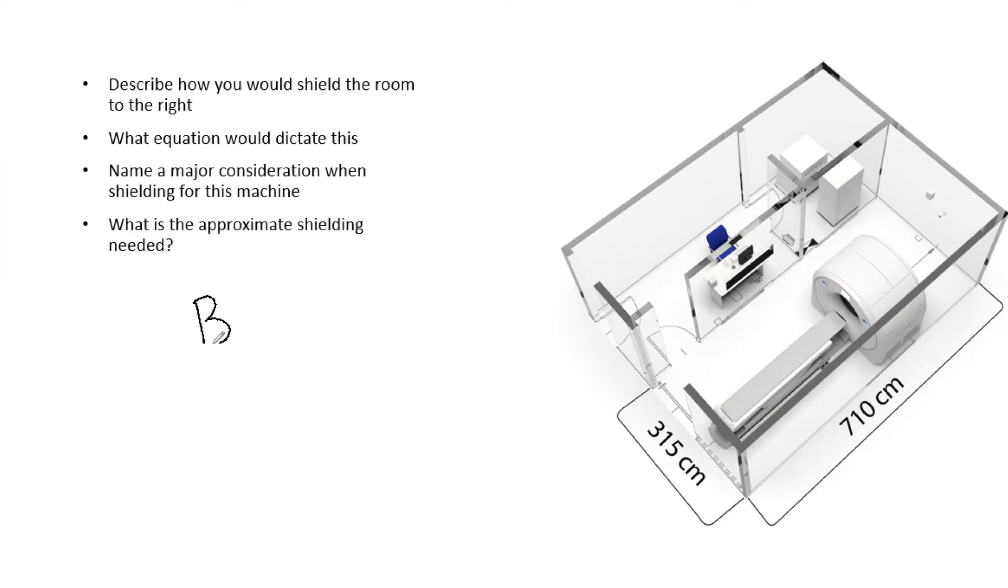To do that, first you need to know the permissible dose P. This is going to vary. It may be 0.1 millisieverts per week for controlled rooms, or 0.02 millisieverts per week for an uncontrolled room or barrier. You also need the workload W. The workload can be slightly different depending on what you are shielding.